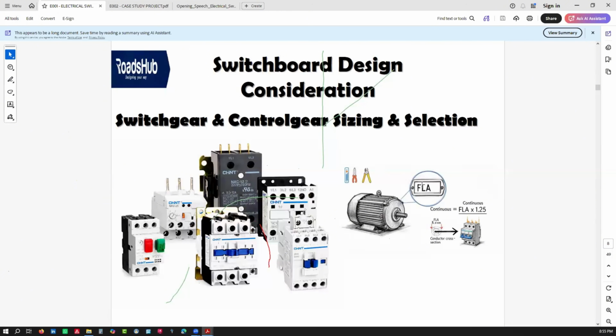So you see, that's a design consideration. Before you select or size any device, you need to be sure this device works on this principle, and this is how I'm going to size it. We have mathematics for that. People come with different ideas. We even have rules of thumb that can help us size a contactor. All those devices need a way to size and select, and that's what we call a switchboard design consideration.